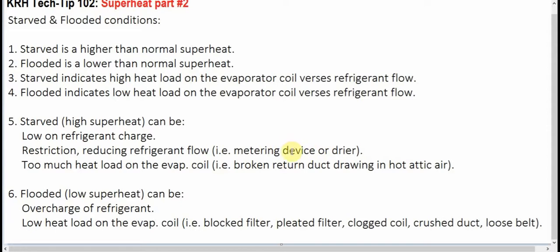Generally, with a restricted dryer, you're going to notice a temperature drop over the dryer when the system is running. When the system is on and it's been running for a few minutes, you want to check the temperature from one side of the dryer to the other. If you notice a temperature drop, then that generally means there is a restriction in that dryer.